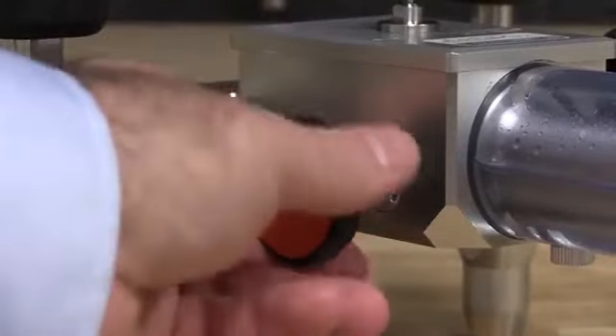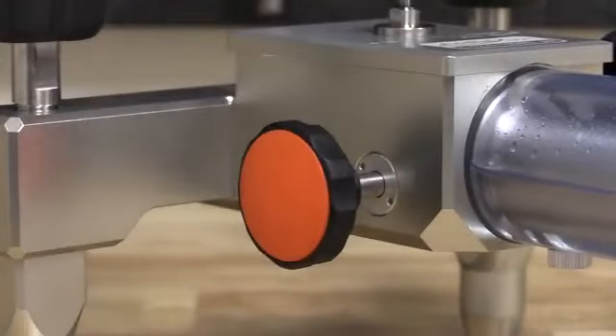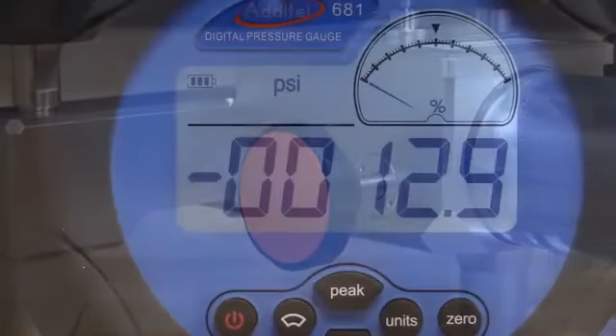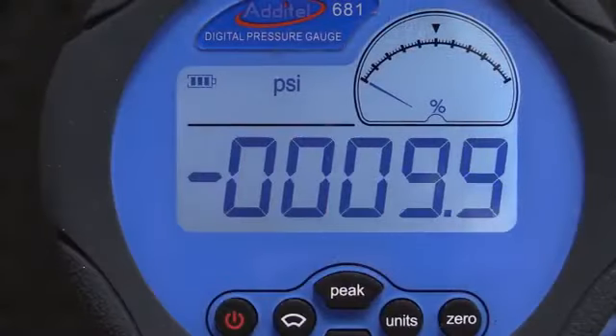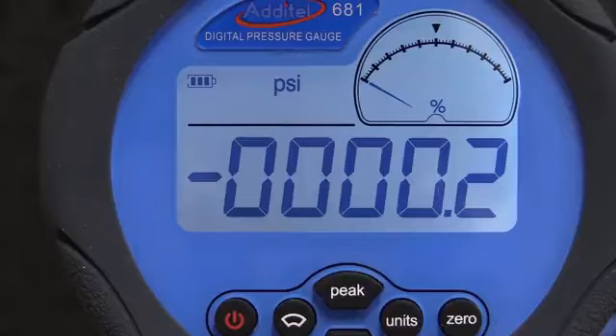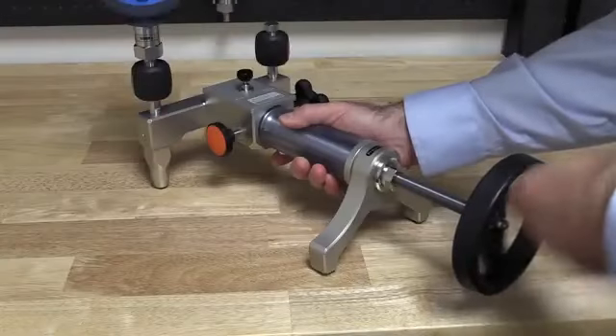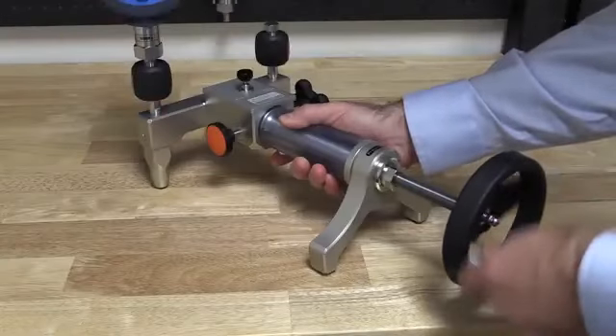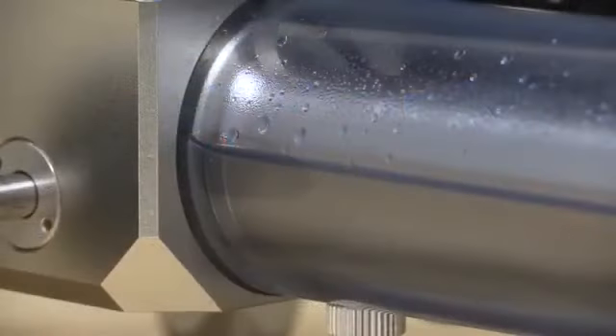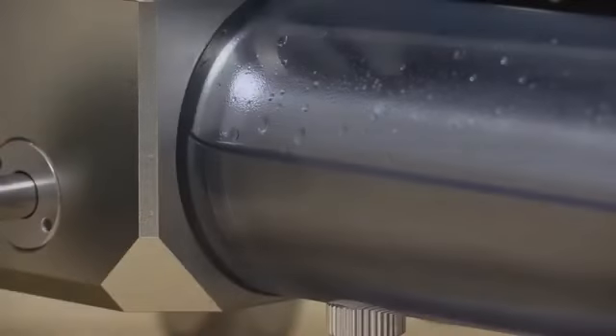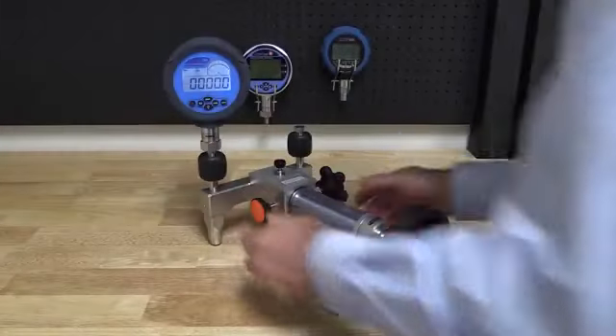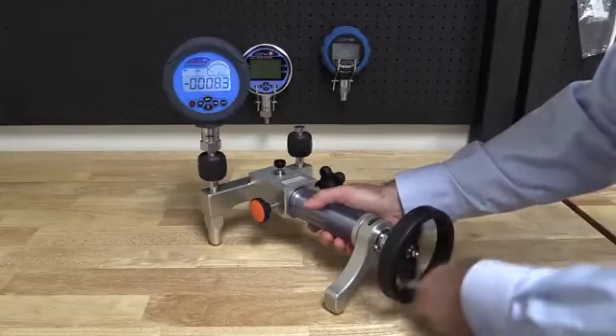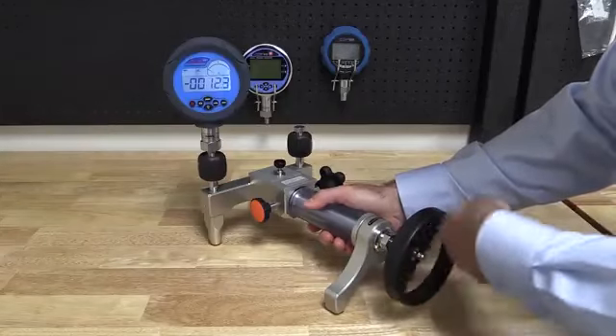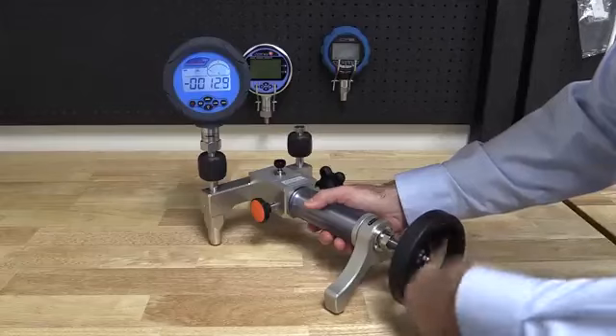Now that we have a vacuum pulled on the system, we will open the vent valve and let fluid fill into the system. You'll notice this by the gauge settling to 0. Now with the vent valve left open, we will turn the main screw press all the way in. If you have gas still in the system, you will notice bubbles coming into the liquid reservoir. Particularly on the initial setup, where there's a lot of gas in the system, the process of pulling a vacuum and purging the gas out of the system will need to be repeated several times.